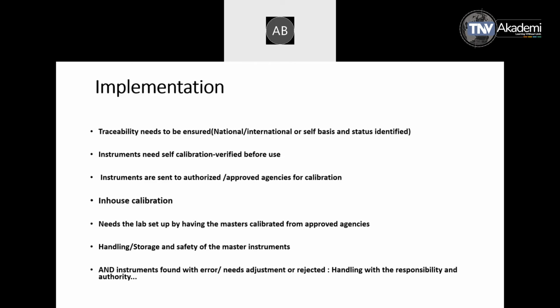If these requirements are not met, if they have not checked the expiry date of the master calibrator, then their own calibration will go wrong. So it is very much a requirement at this stage. We also have a situation where a lot of in-house calibrations are being done today in manufacturing and assembly organizations. So it is good to set up an in-house calibration. It saves time, and it also makes the inspection and QA/QC team knowledgeable.